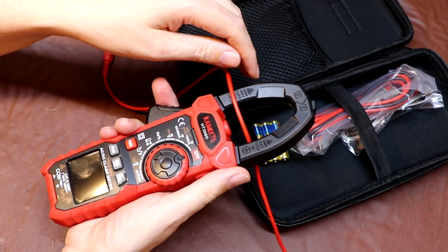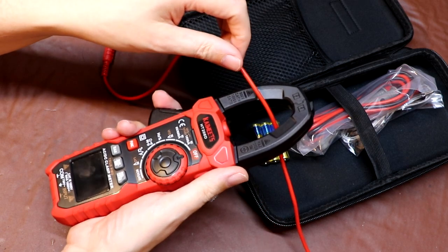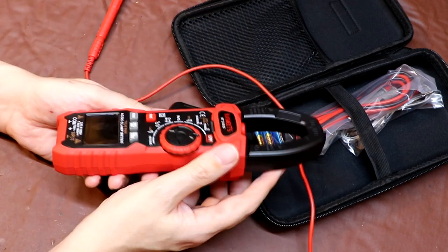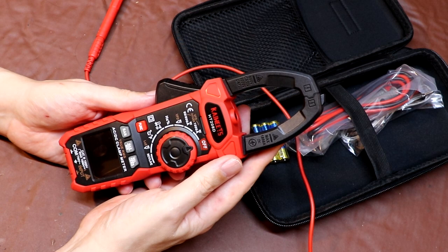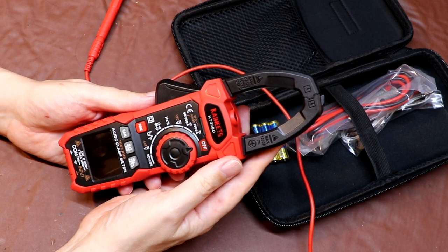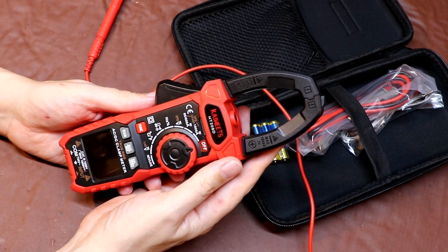And when you finish making the current measurements, the only thing you've got to do is just open the clamps and remove the wire. So as you can see, this really is a major safety advantage if you're working on circuits or maybe control panels that operate at high voltage or where there's a potential for a very, very high fault current.